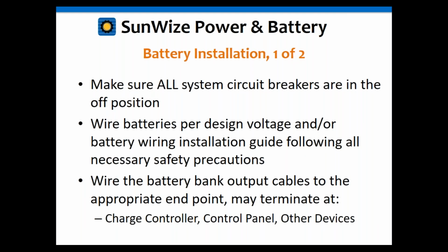You want to wire the batteries per the design voltage, following the wiring guide. It's going to tell you what should be in series and parallel. You should have a wiring diagram with the batteries for the system. You want to make certain that the battery cables are taken to the appropriate endpoint and terminated, whether it be the charge controller, control panel, or some other type of battery parallel distribution box or something like that.